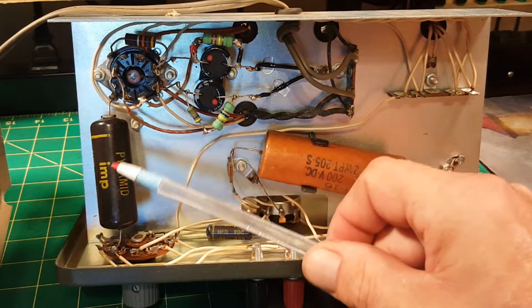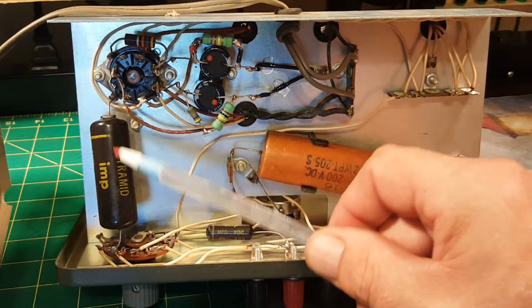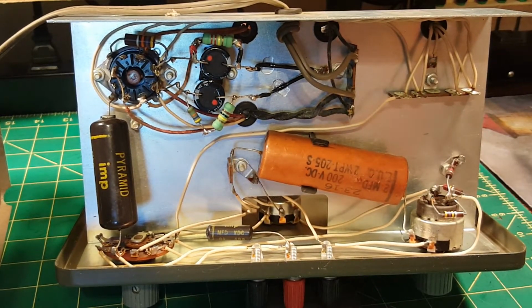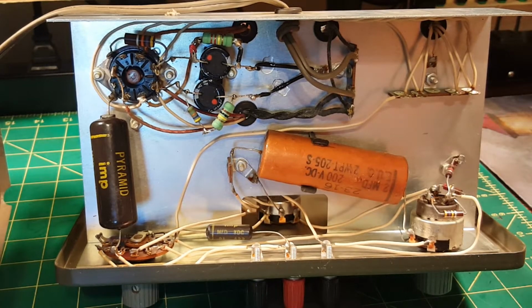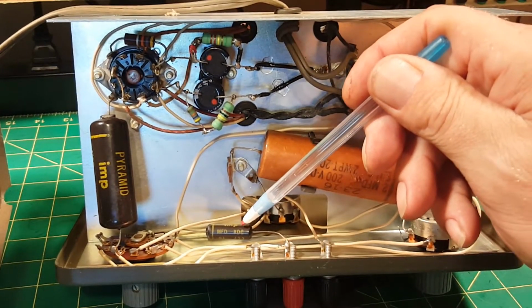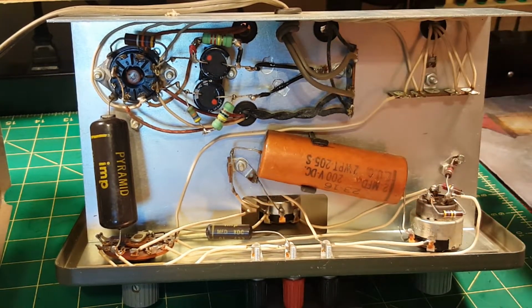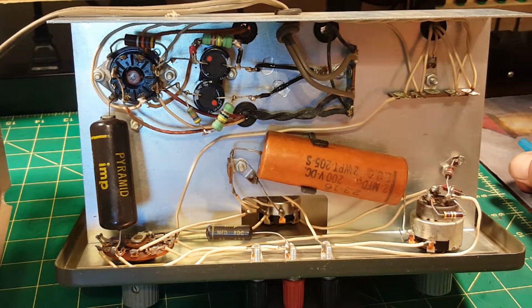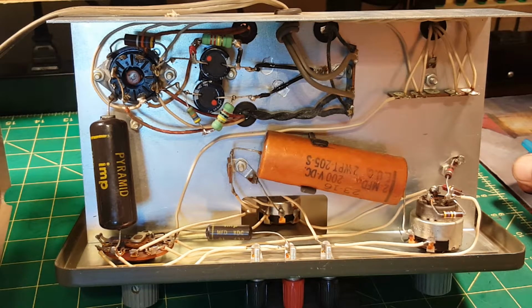How many of these molded capacitors are there? I've already tested that one - it's fine, but it's got to go. They like to fail. And this one down here is in series with your test lead that you connect to your capacitor. You don't want that cap to fail. It's getting replaced - anything that might impact safety gets replaced.